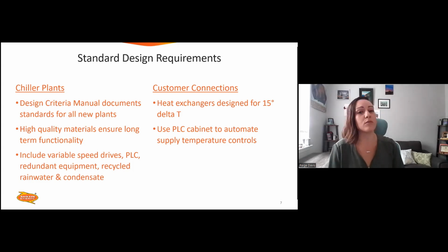So every customer is connected to the system via a heat exchanger that's designed for a 15-degree delta T. And that just helps make sure that we're getting the right return temperatures back to the plant so that we can operate at full capacity and minimize any excess flow in the system. And in downtown, actually, making improvements in our customer delta temperatures has helped us to increase the average system return temperatures by about 4 degrees. So system-wide, that's a pretty significant increase. And like I said, that just helps make sure that we have our full plant capacity available when we need it.